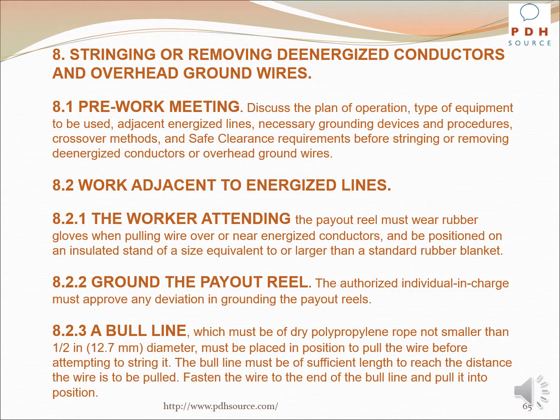Now some comments on stringing or removing de-energized conductors and overhead ground wires. A pre-work meeting: discuss the plan of operation, type of equipment to be used, adjacent energized lines, necessary grounding devices and procedures, crossover methods, and safe clearance requirements before stringing or removing de-energized conductors or overhead ground wires.